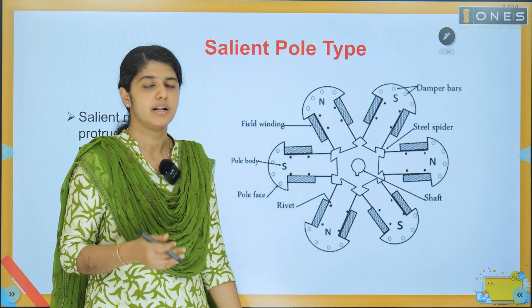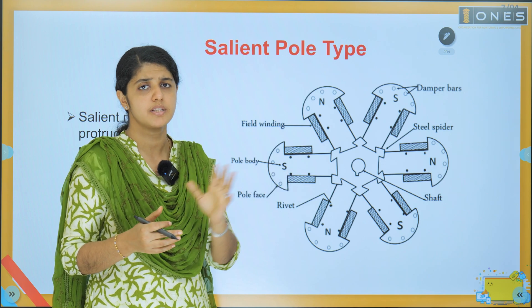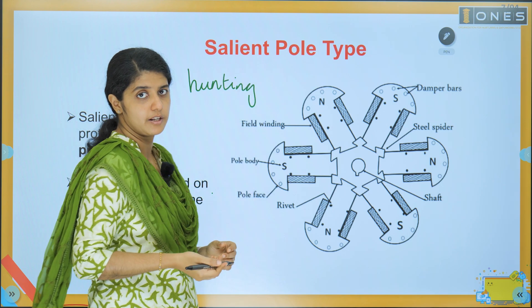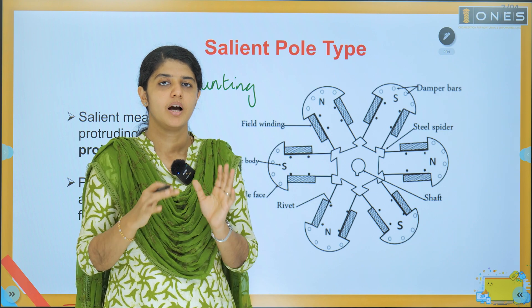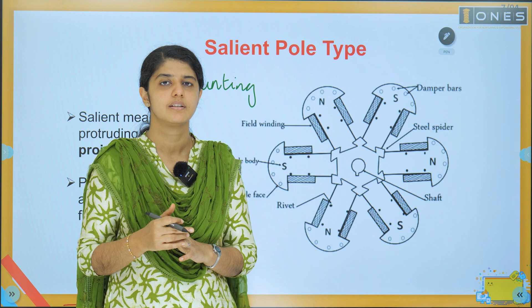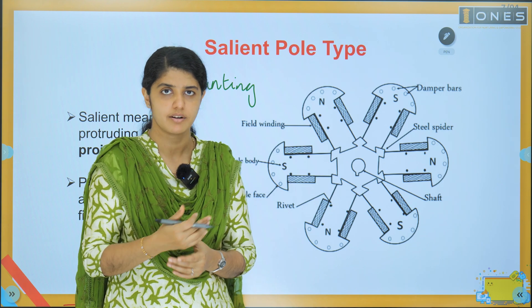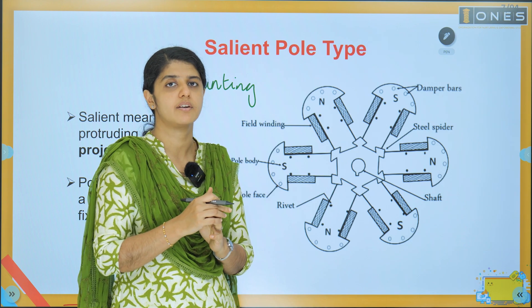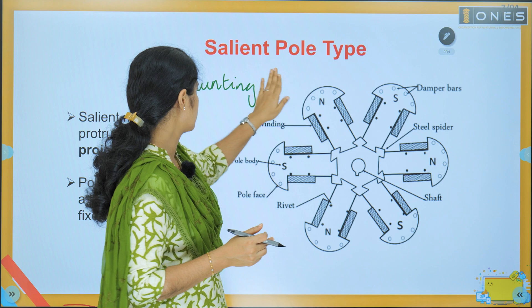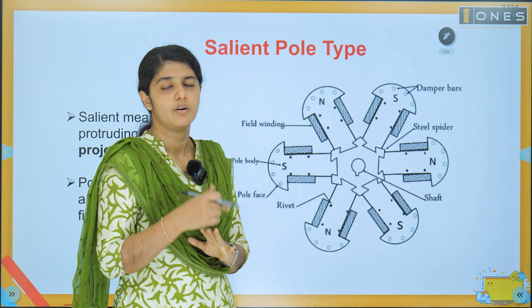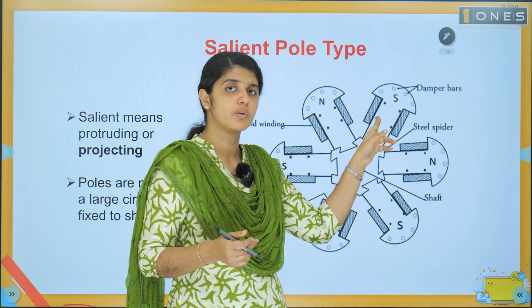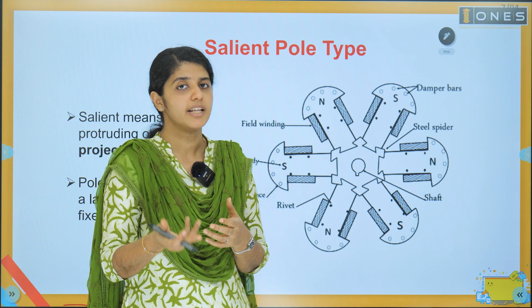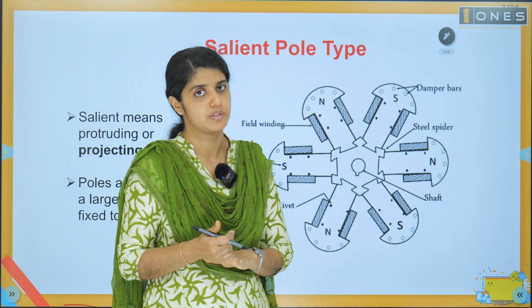The damper bar in the salient pole type has three separate functions. First, it can damp out rotor oscillations. Second, it can suppress voltage fluctuations and voltage variations in the alternator. Third, it can be used as a self-starting method — we can use this damper bar as an induction motor for starting.